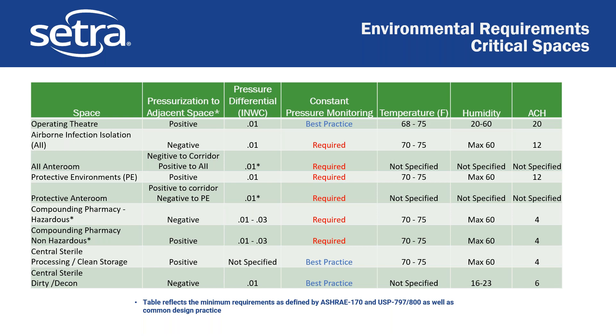You do not necessarily have to have local monitoring for temp and humidity, but you do for pressurization, because this manages contaminants and infection more than the temp and humidity portions do. Operating theaters have very high air changes per hour — important to make sure that if there are contaminants in the air they get cleared out quickly. Anterooms are also specified: each room relative to the adjacent space has to have a pressure differential, which we'll talk through in the applications.